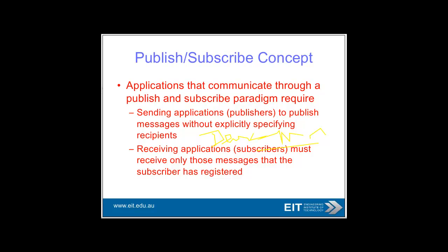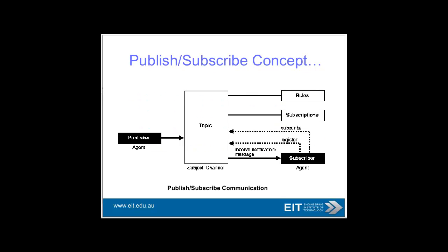The publisher-subscribe model works so that you have various publishers of information — for example, an instrument gathering flow information or current data — that publishes on the bus at a particular defined interval. Then you have subscribers who subscribe to that data and use it in their application. You sometimes hear it called producer-consumer. This is a very important part of the whole substation automation world.